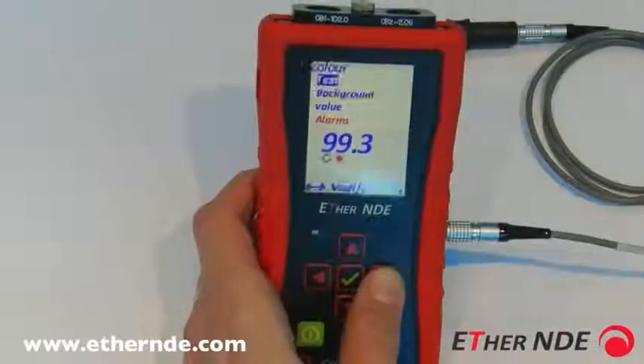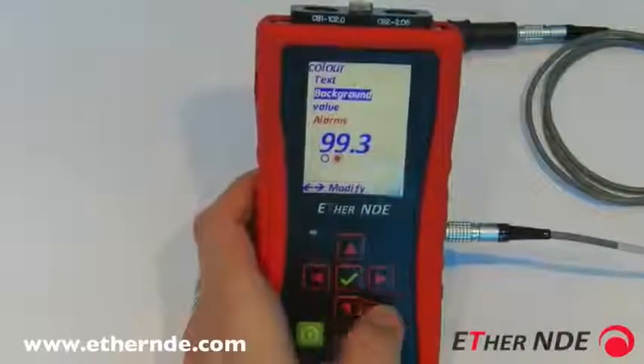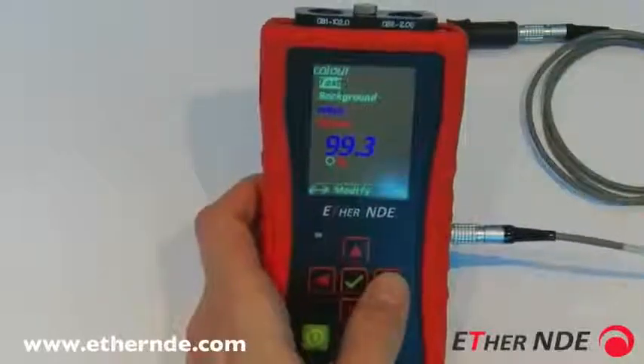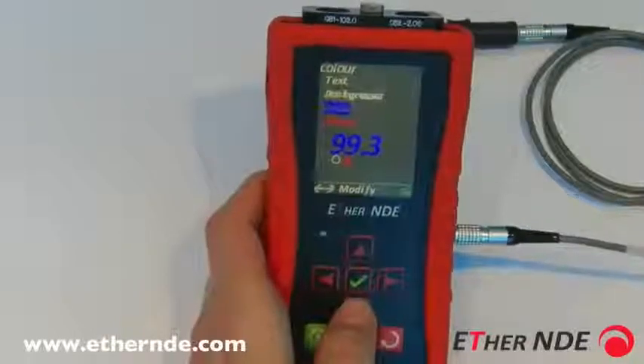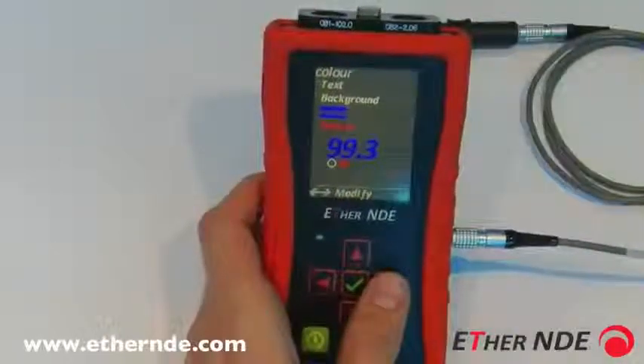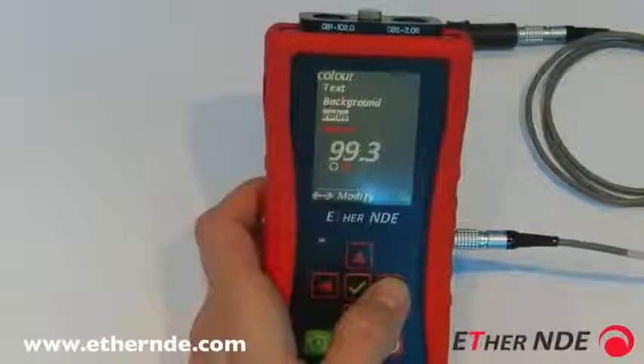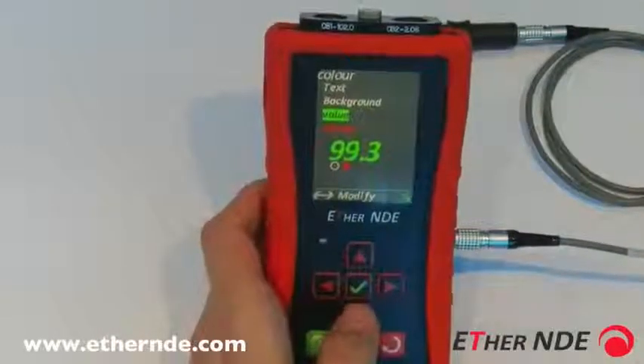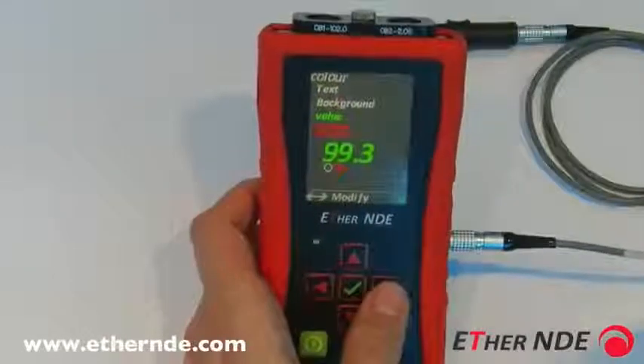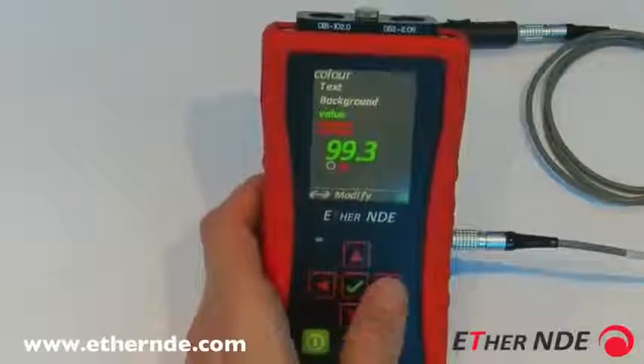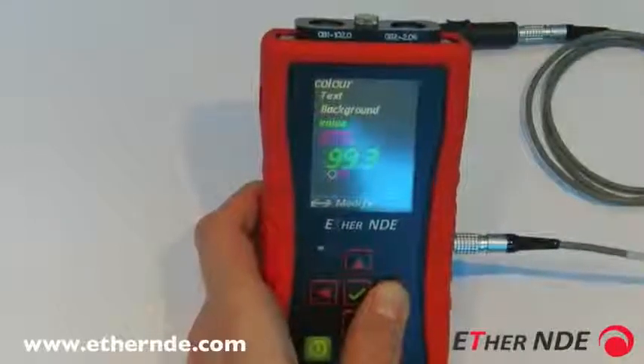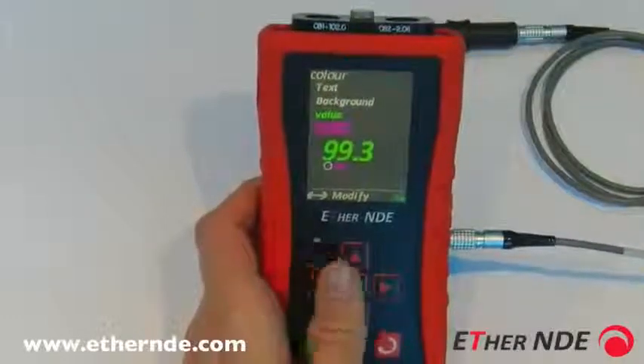Changing the text color will change the majority of the screen text. If we pick a different color scheme — blue — we can now change the background, which currently is a cream color, so we pick gray. We can now change the text color to white. The values color is the color scheme normally used for your everyday readings, such as conductivity or liftoff. Let's set that to a brighter green.